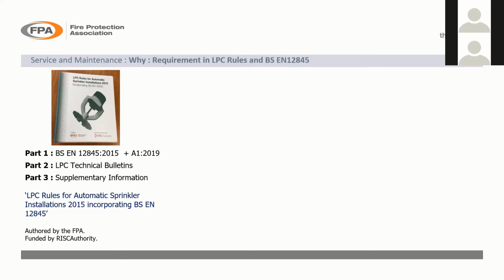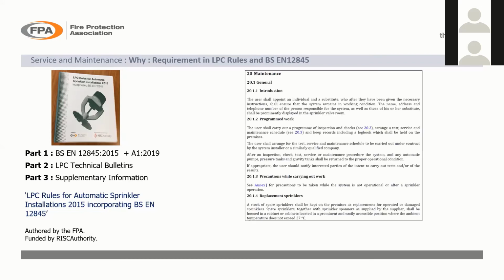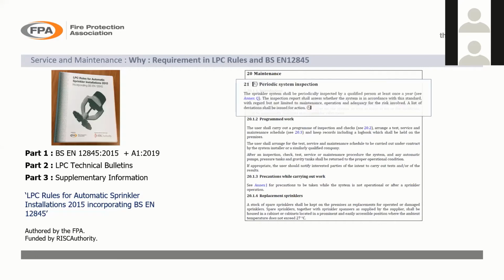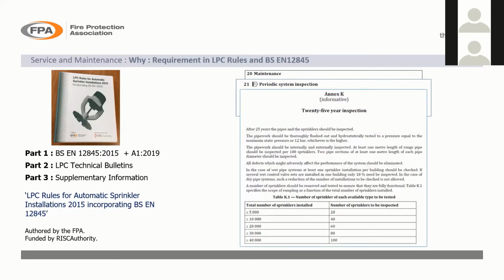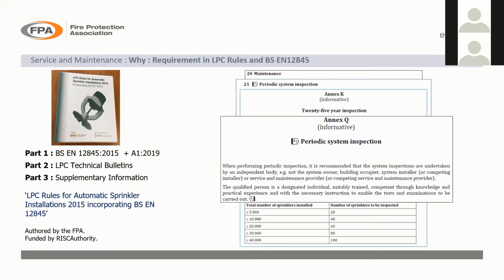But in Parts 1 and 2, the requirements for maintenance come from section 20, which covers maintenance of sprinkler systems, and section 21, which covers the periodic inspection of the systems, which I'll come on to later. Just bear with me a second. And Annex K, which covers the 25-year inspections, and Annex Q, which also covers the periodic system inspections. If you don't have a copy of the LPC rules, you can obtain these from the FPA, and just let us know, and we can provide a price for supplying those to you.